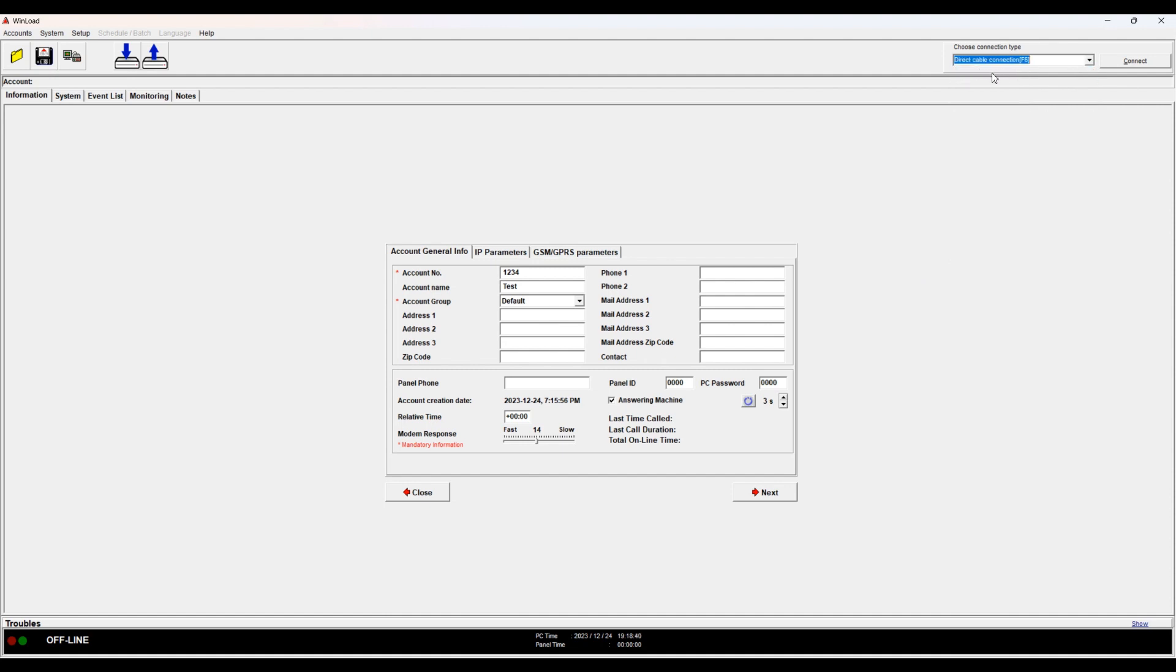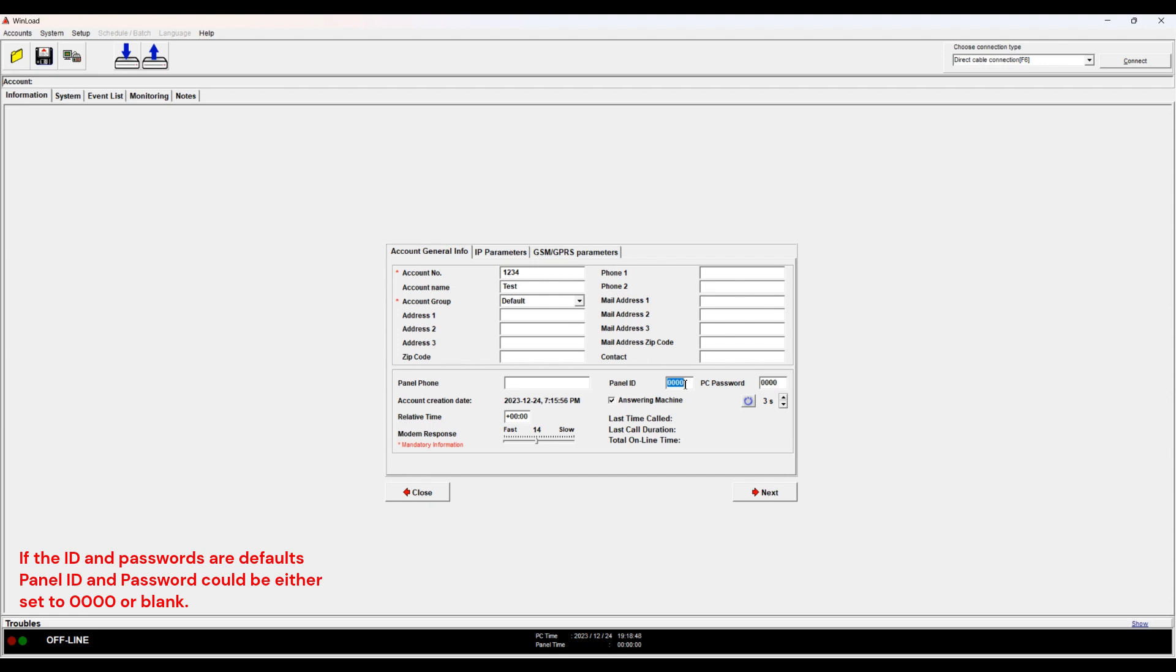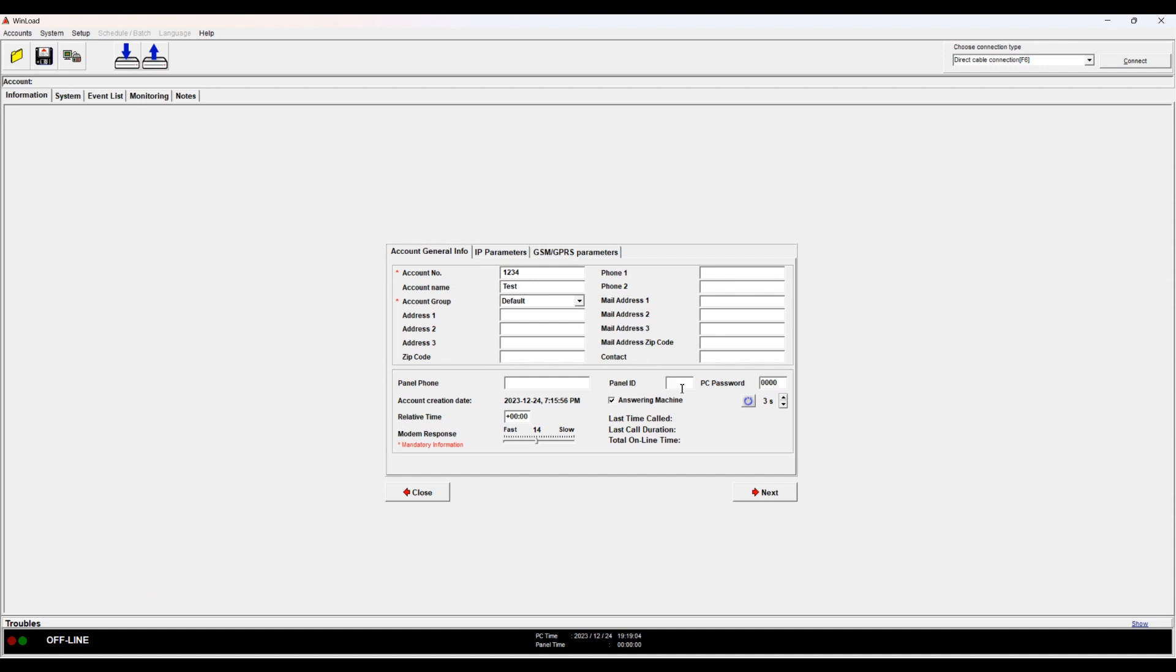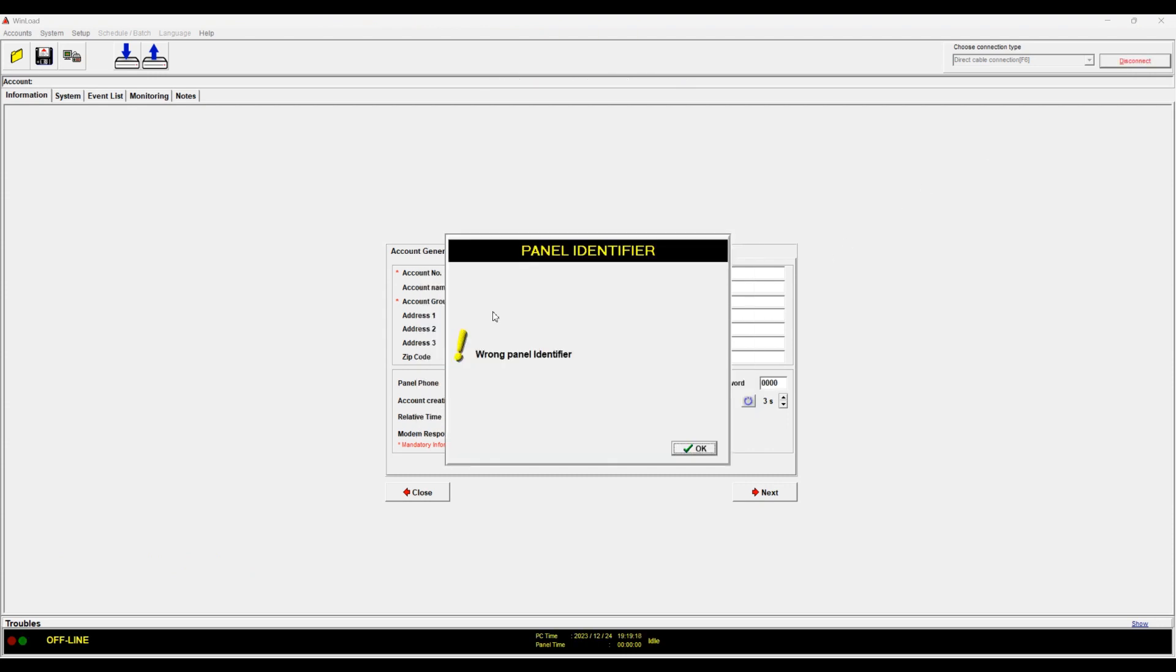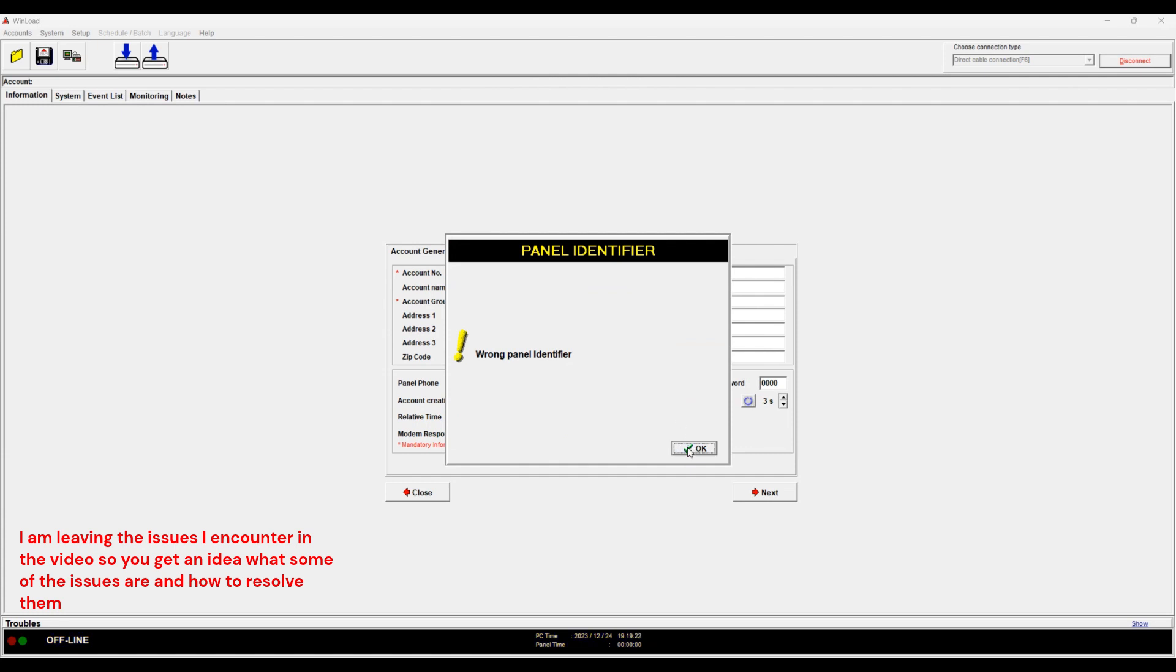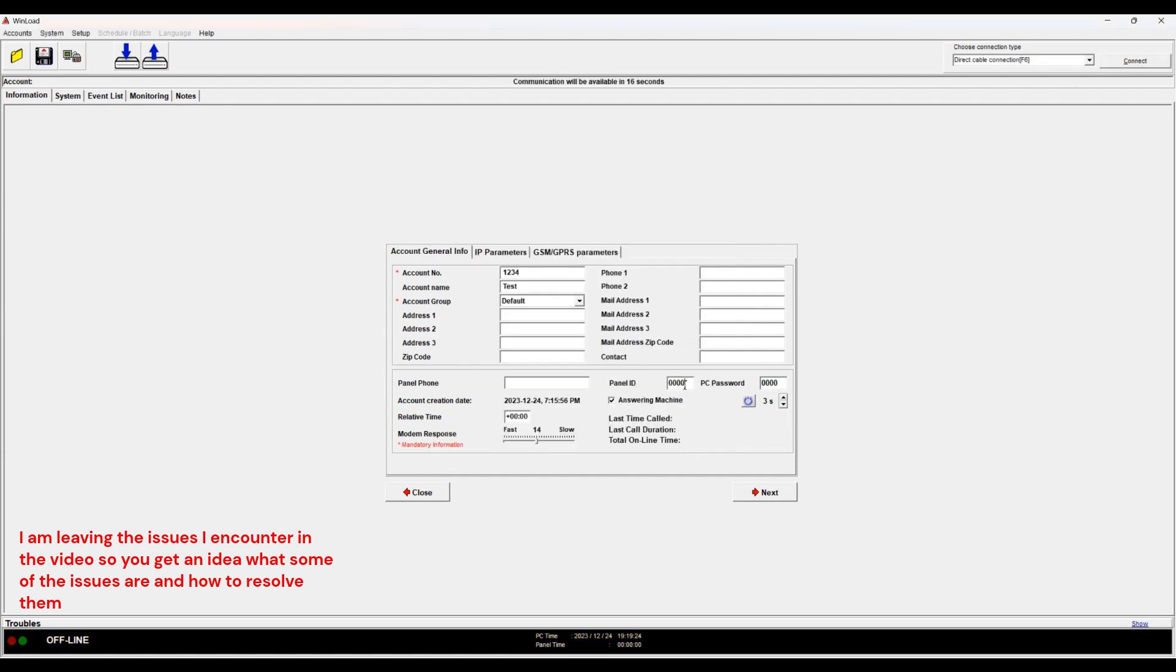For this panel ID, because my panel doesn't have an ID, like the ID is 0000 and password is four zeros. Sometimes when this is not set, you have to put zeros or you leave it blank, but just so you know. Usually you don't leave this empty, so you shouldn't run into issues. So connect. Now it's trying to open the port. Wrong panel identifier. This is what I was talking about. So let's try without the zeros.